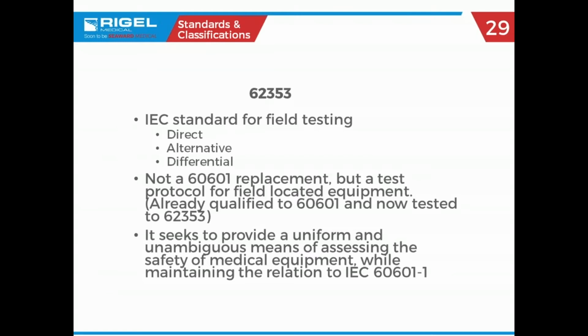Now, over time, hopefully you have that record history that justifies how you can shorten your test times. So it all depends on what your hospital process is. If it says we test to manufacturer specification, then you're going to be doing reverse polarity. Didn't the FDA just pass that mandate last year? You have to do everything the manufacturer says unless you have an alternative backup. So there are AEM programs, right? Alternative equipment maintenance. But NFPA 99, 2018, in fact it went back to the 2012 edition, no, you don't have to do it if you're testing to the NFPA 99 standard.